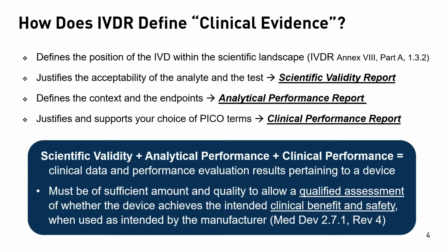So for many companies, you may have prior experience with the FDA 510K submissions for your devices. So you may actually already have some of the elements for the PER in place. However, the PER must support the clinical benefit of the IVD test, which is a new requirement. And there will most likely be additional data that will need to be generated and gathered as appropriate.